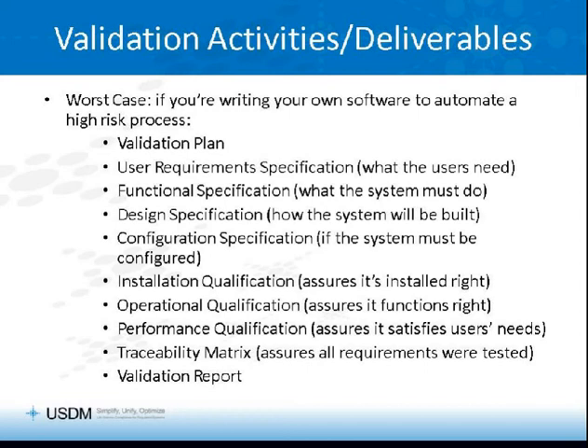You'll need that user requirement specification that says what the users need, the functional spec that says what the system must do, a design specification saying how the system will be built to do it, possibly a configuration specification to capture configuration settings if the system is going to be configured, an IQ to ensure that it's installed correctly, an OQ to assure that its software functions correctly, and a PQ, or performance qualification, that goes back to the user requirements and verifies that it properly automates the user's process or manages properly the user's regulated records.